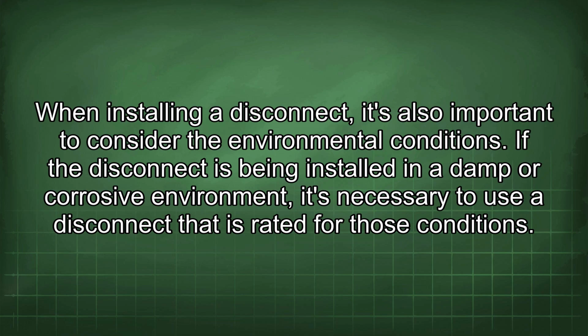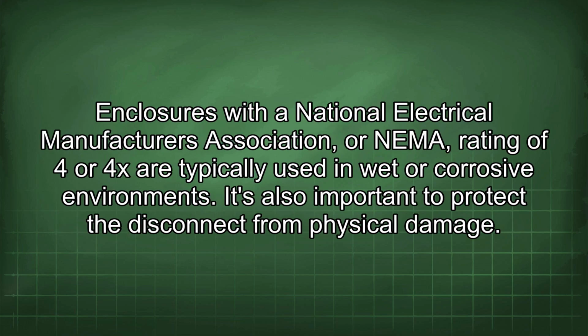When installing a disconnect, it's also important to consider the environmental conditions. If the disconnect is being installed in a damp or corrosive environment, it's necessary to use a disconnect that is rated for those conditions. Enclosures with the National Electrical Manufacturers Association, or NEMA, rating of 4 or 4X are typically used in wet or corrosive environments.